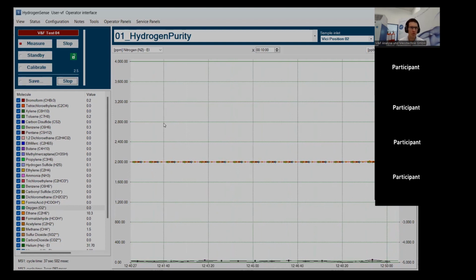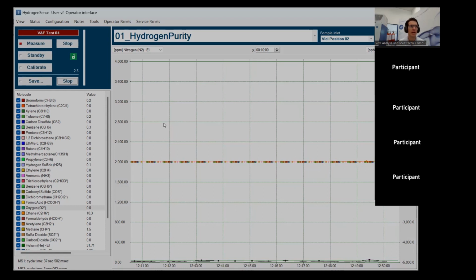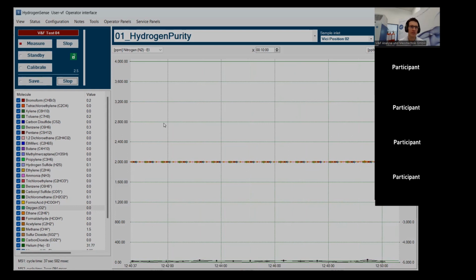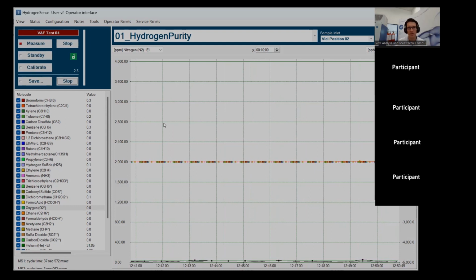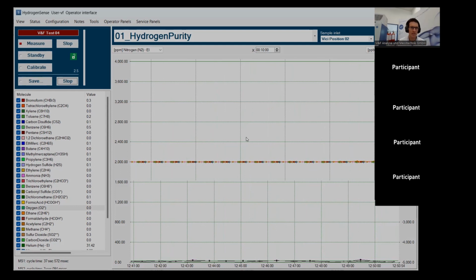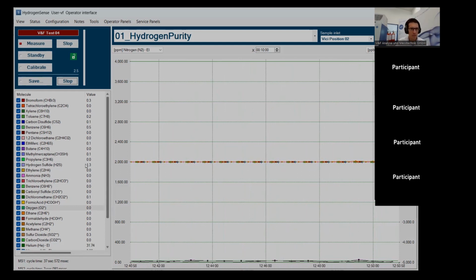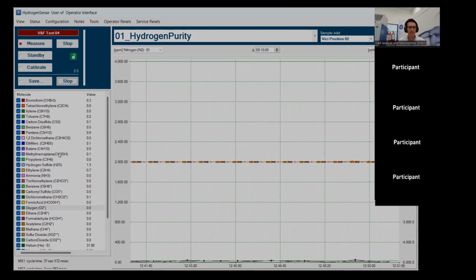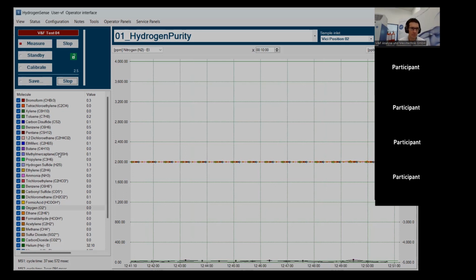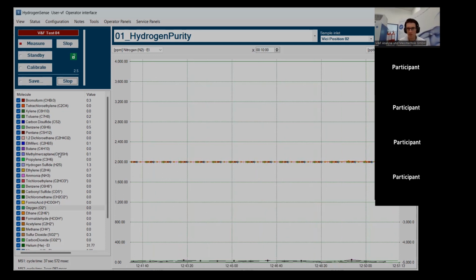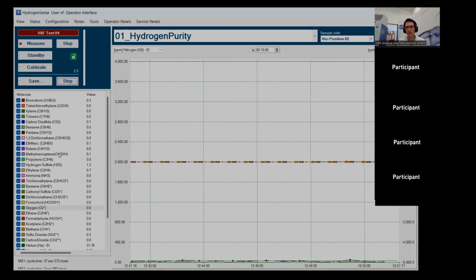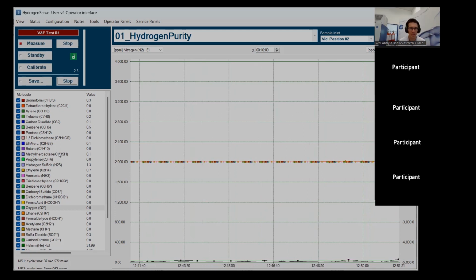Because sometimes when you look at an application like this, the first intention would be, all right, I want to quantify 4 ppb of total sulfur, so I take 3 compounds and put, let's say, 2 ppb of each into the calibration gas. This is very difficult for a gas manufacturer to produce. Producing a ppb standard is very, very difficult. The good thing about our instruments is that they are linear over a vast range. As you've seen before, we typically use calibration gases in the ppm range, because we can demonstrate that when I, for example, calibrate methyl mercaptan at 1 ppm, I will still get accurate results at 5 ppb. It makes it much easier for the calibration gas manufacturer to make a 1 ppm gas than a 2 ppb gas.